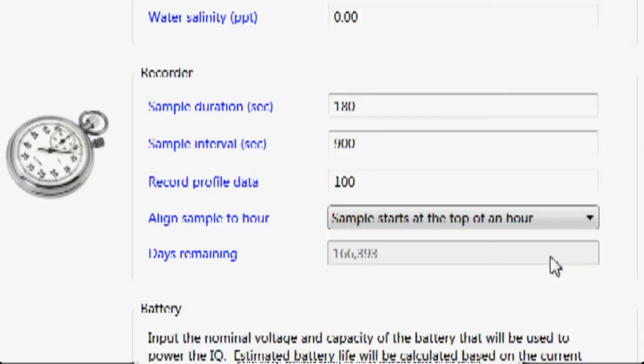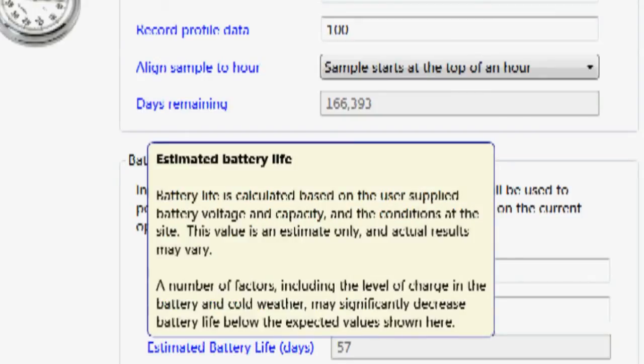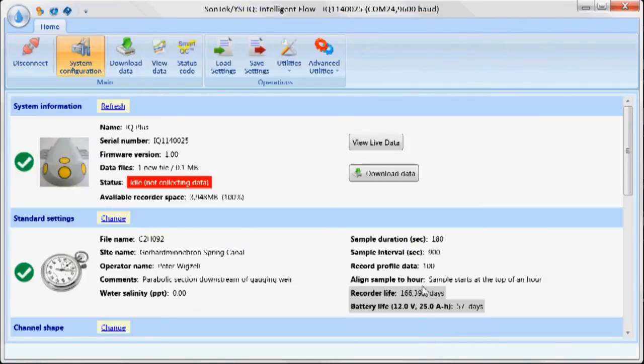The align to sample hour. We have three choices. First of all, do not align. We can set the sample to start at the top of the hour or at the end of the hour. In this case, I'll set it to start at the top of the hour. It gives me the days remaining. The battery power is next. This basically gives you an estimate of our power consumption. Here we're using a 12 volt battery. We've got a 20 amp hour battery, and it basically is telling me I have about 46 days left of the recorder. So once I've entered all that information, it sends that to the IQ and it's programmed.